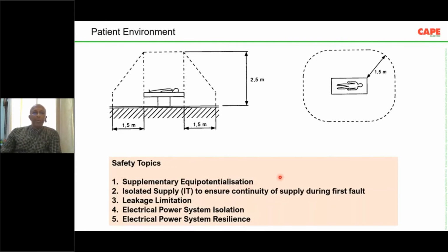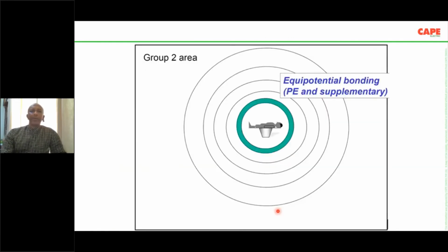What do you mean by supplementary equipotential bonding? This means you have different kinds of metallic objects, including your equipment, maybe the table, or maybe the wash basin, the pipes, and so on. Every metal part in that location shall be interconnected in such a way that the potential difference during normal operation is lesser than about, I think, 20 millivolt or 30 millivolt, a very, very small value. Isolated supply is required. Now, patient environment. The first safety measure I want to tell you is called equipotential bonding, protective equipotential bonding.